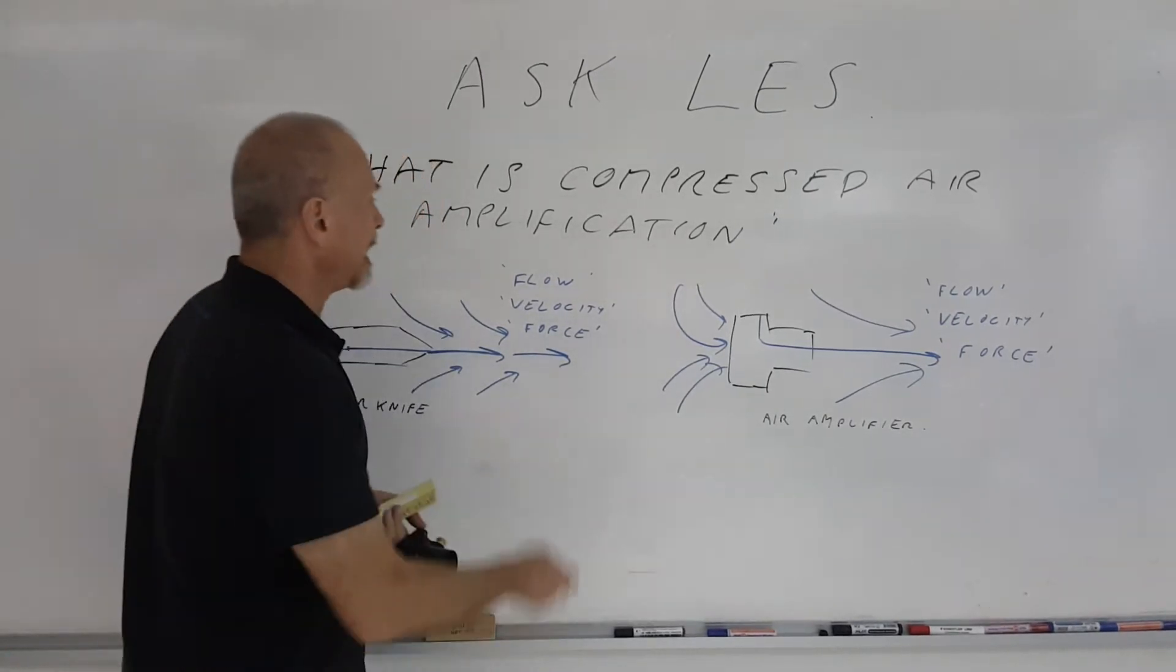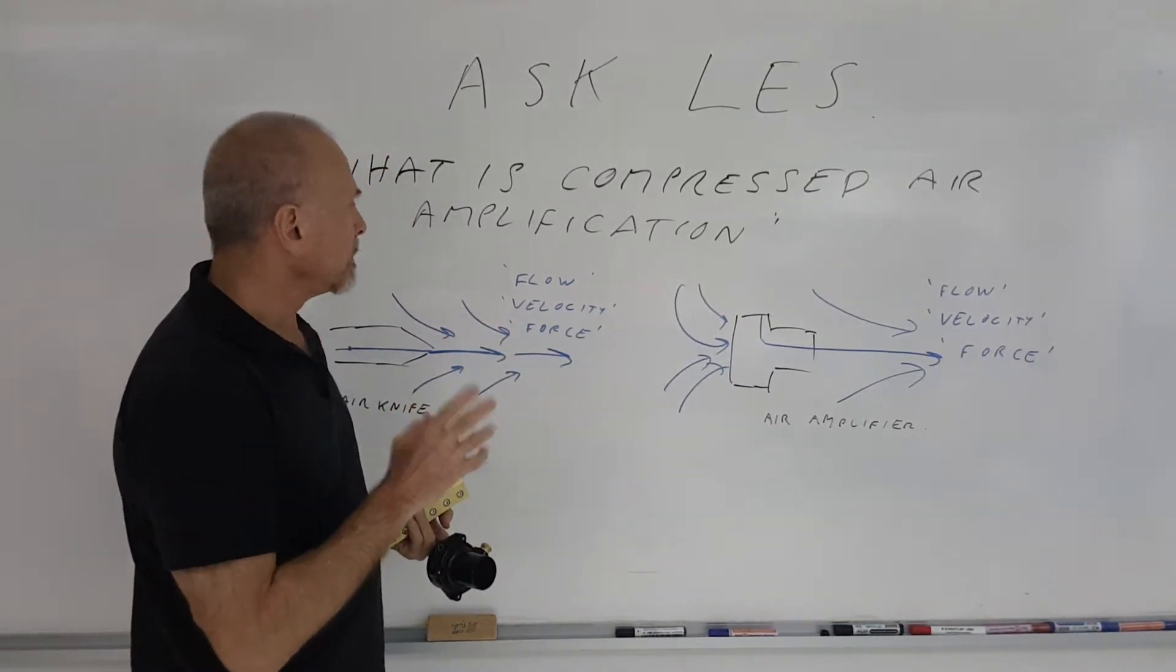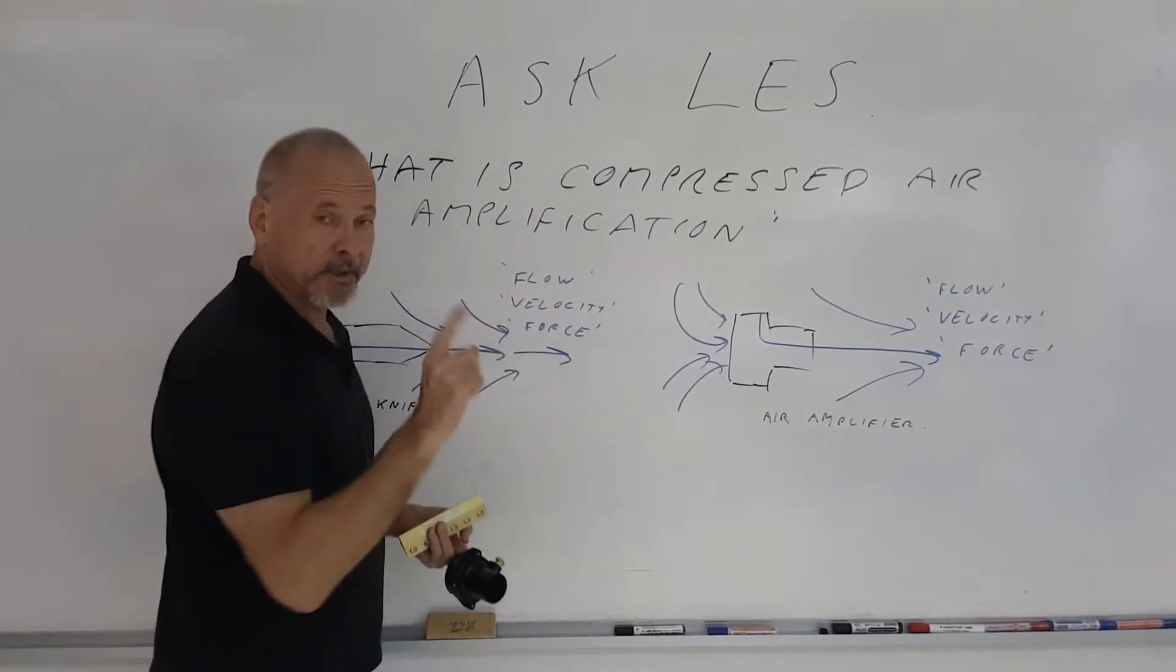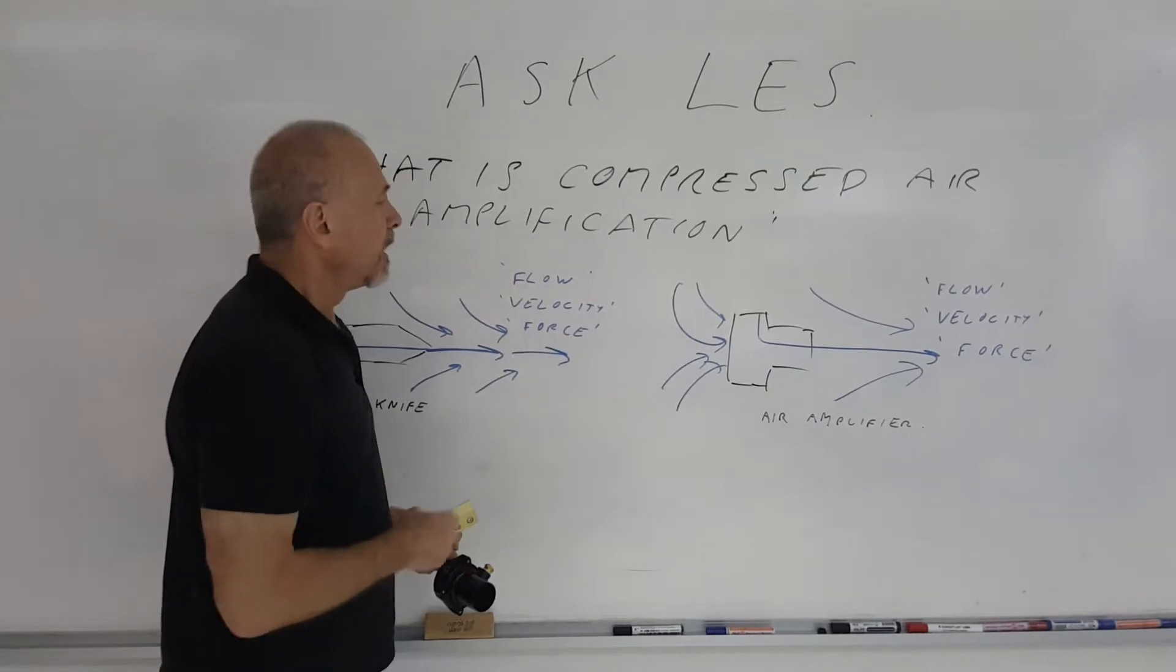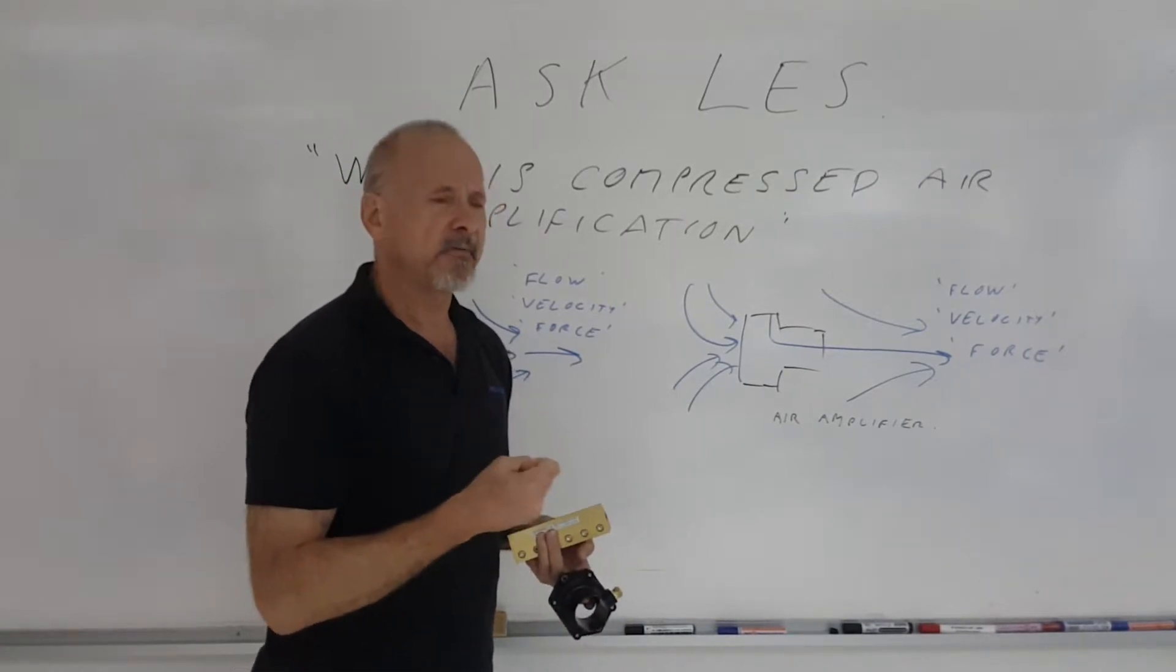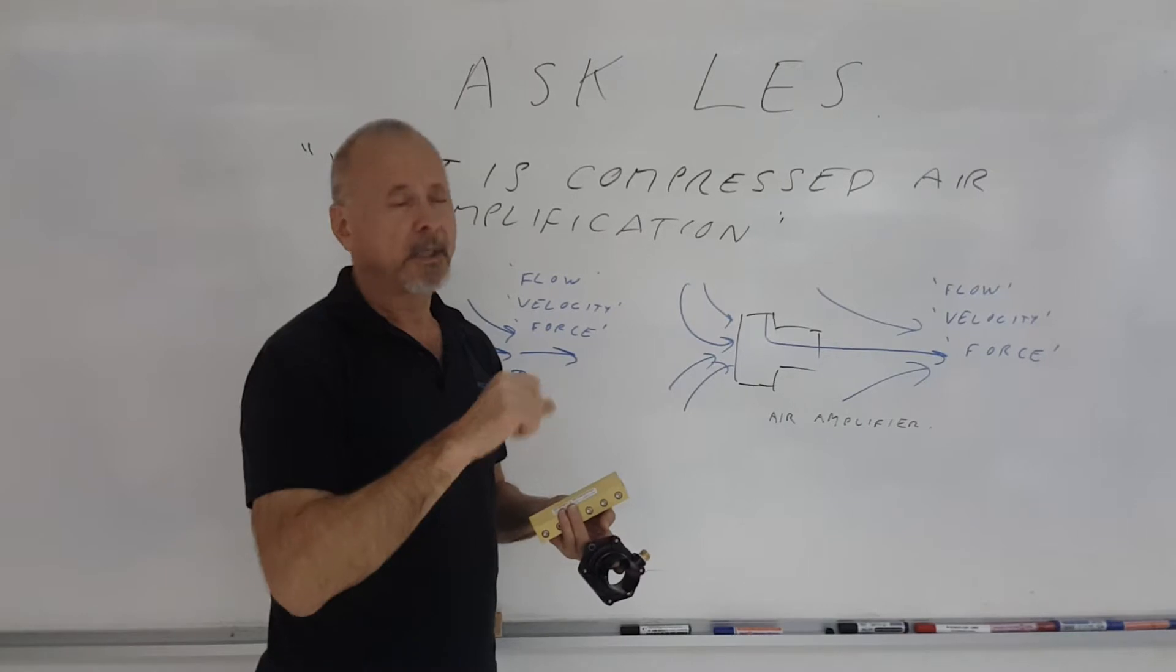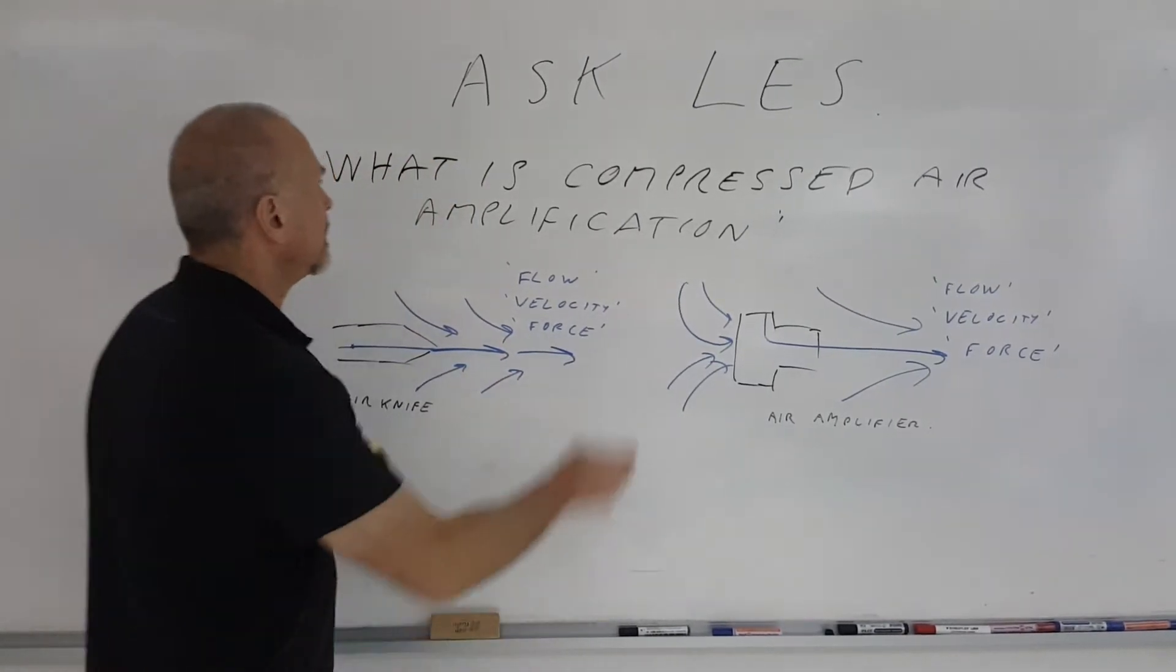What's important is the flow that's produced and also the air consumption, the velocity, and the force produced. A real, more honest determination of efficiency and effectiveness is the force per CFM consumed. That's a much better determination of how well a product really works, not the term compressed air amplification. However, that kind of explains what it is.